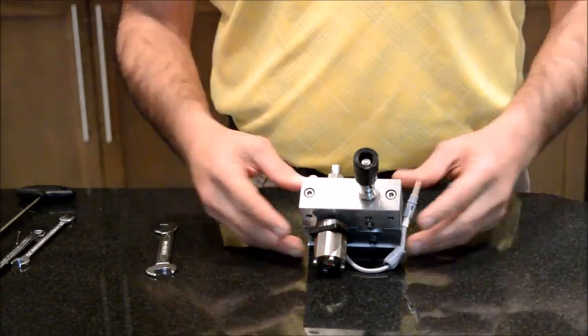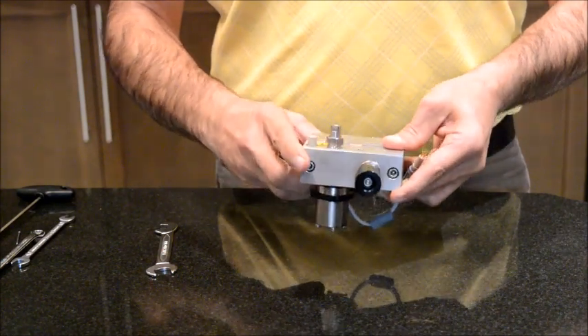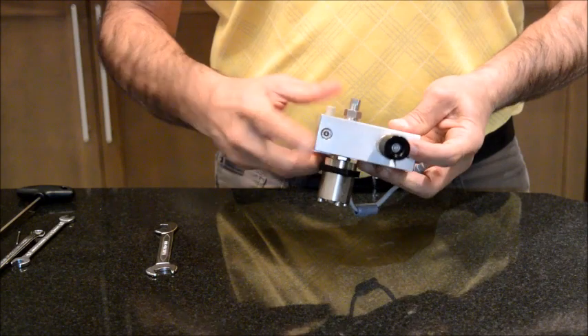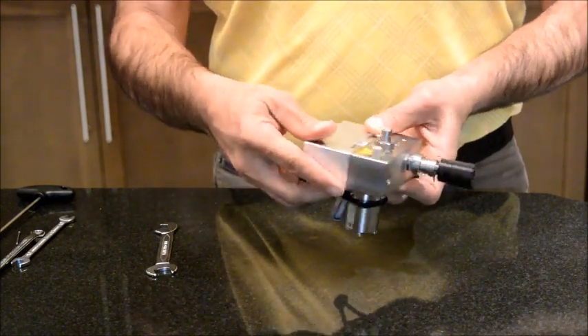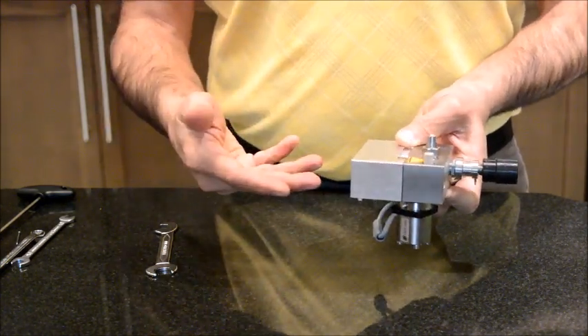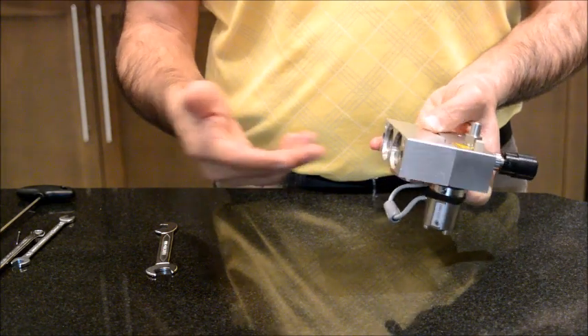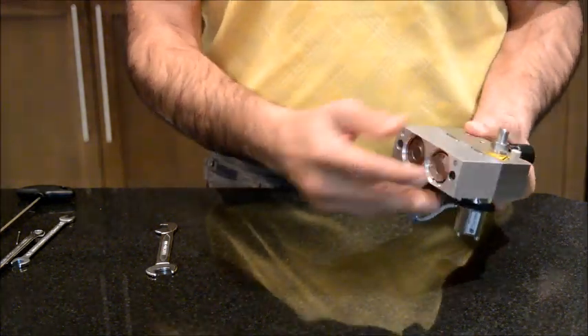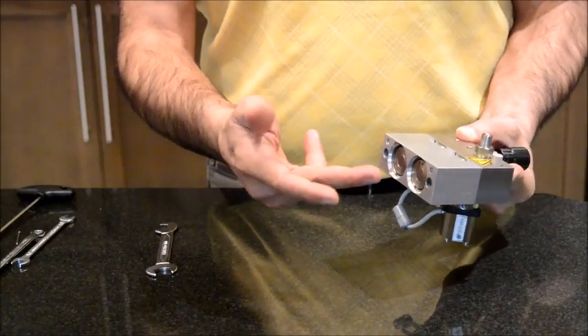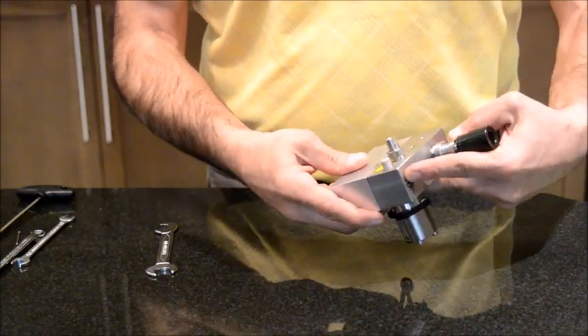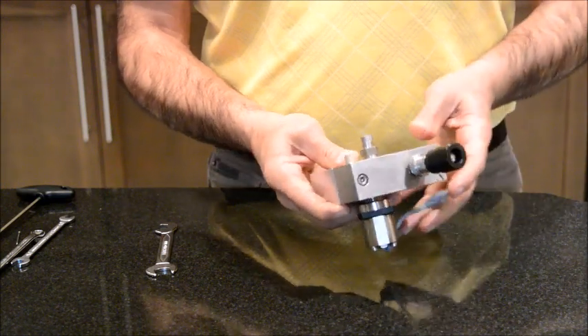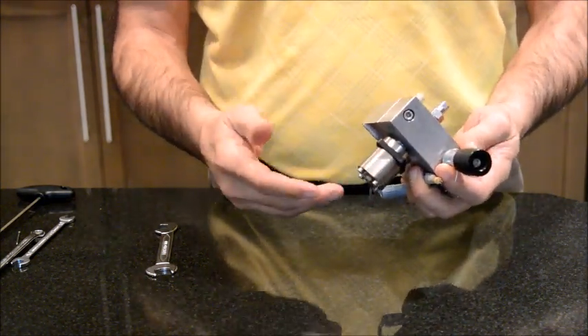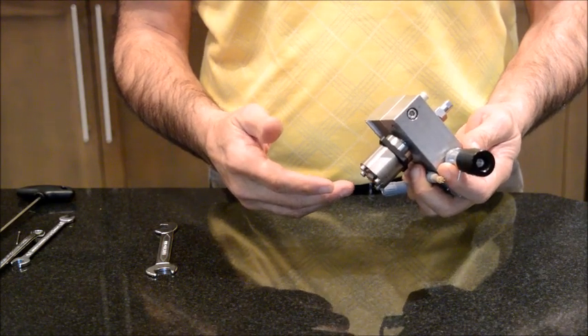What I have here is the Agilent HPLC 1100 pump head. They call it pump head because it is sitting on top of a motor which is doing the actuation, and this motor pushes these pistons that you see at the back and then they will make the flow going to the HPLC. I will talk about the components of this pump head one by one and I will talk about the problems that you may face that are related to these components of this piece.